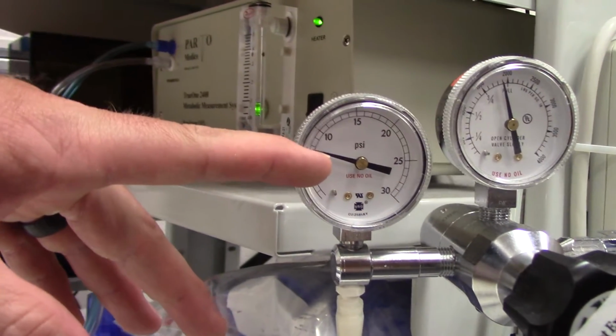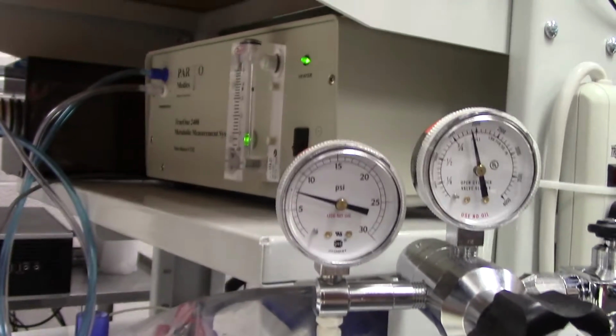We should see some live values here. That's the pressure that's being drawn. That's the total amount of air left inside of the actual tank. So, it's going for its steady flow. Right now this is ambient air, so it should be just under 20% oxygen and about 0.04, but like anything else, that's why we're calibrating, because it's going to make some mistakes.